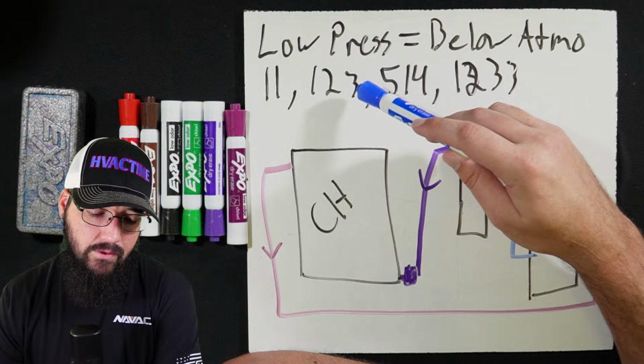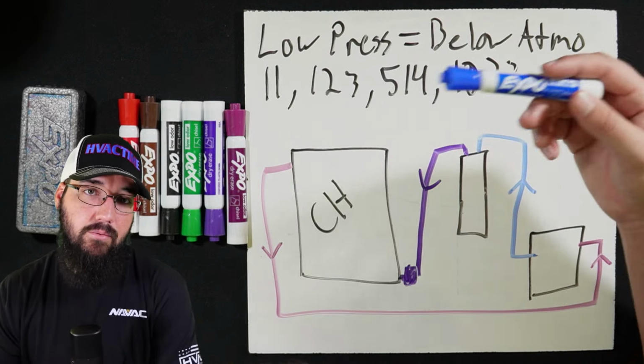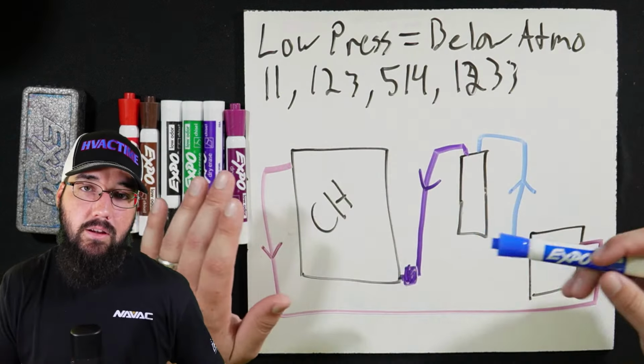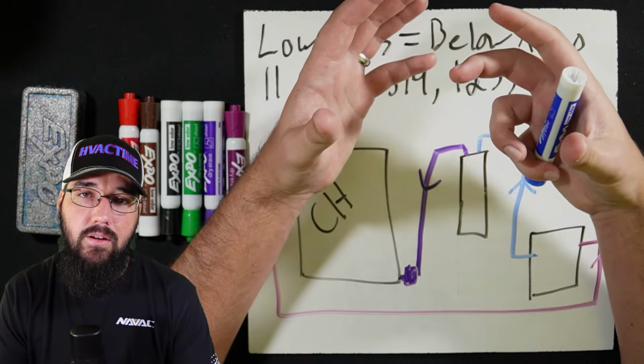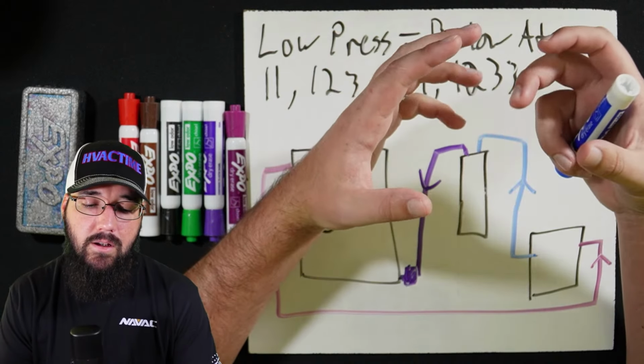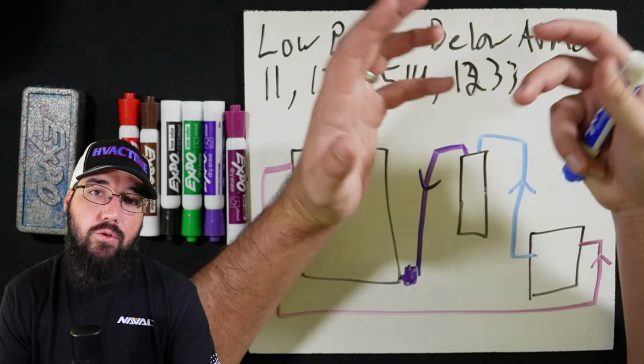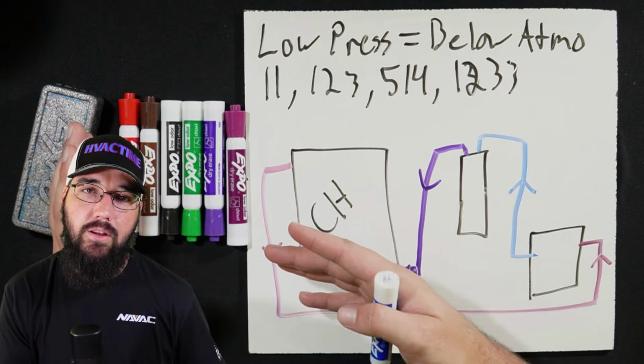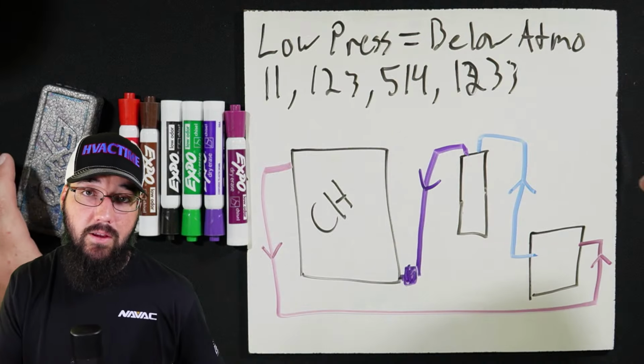And the way you get that refrigerant from A to B is you put an adapter on the tank, then you just hold it up and gravity feed that refrigerant into the chiller. So that is a method.